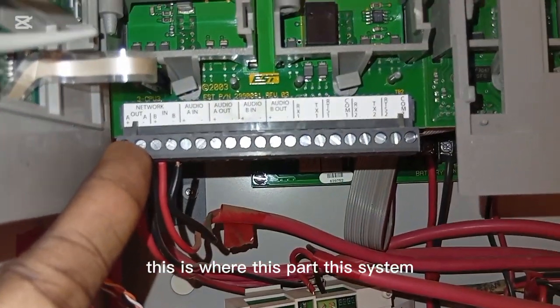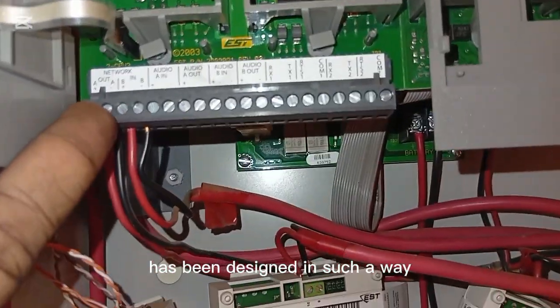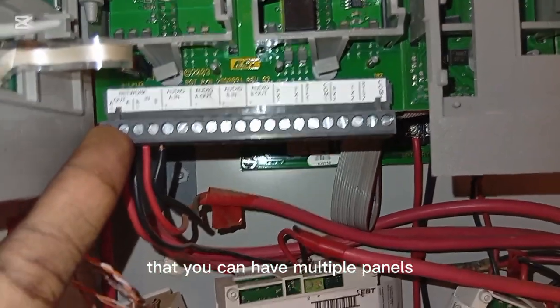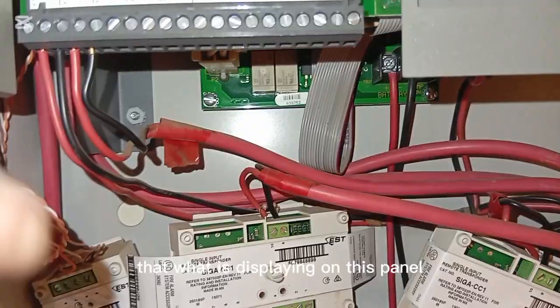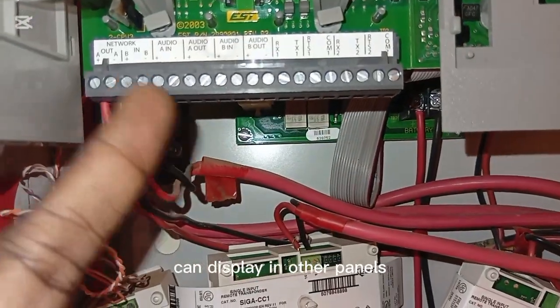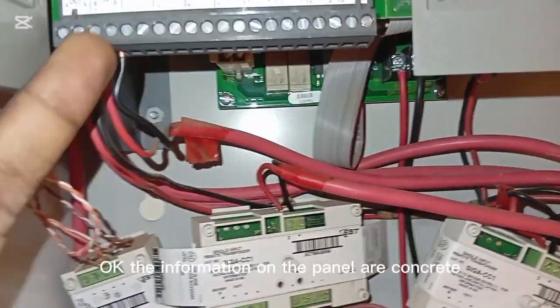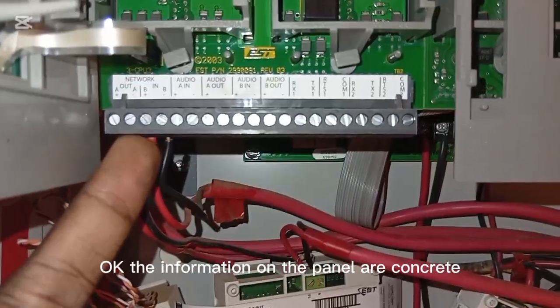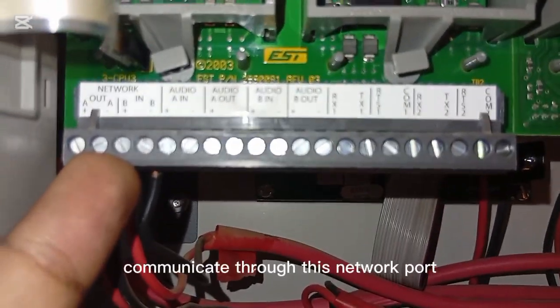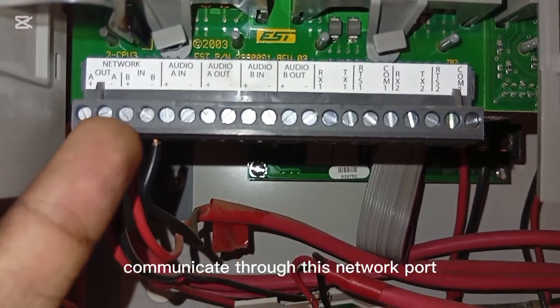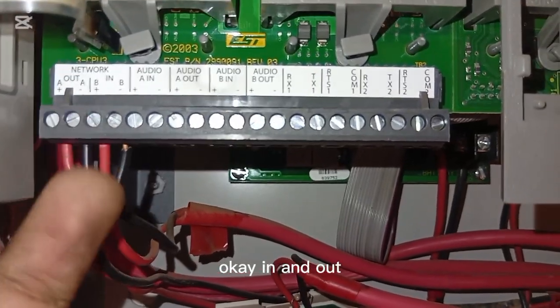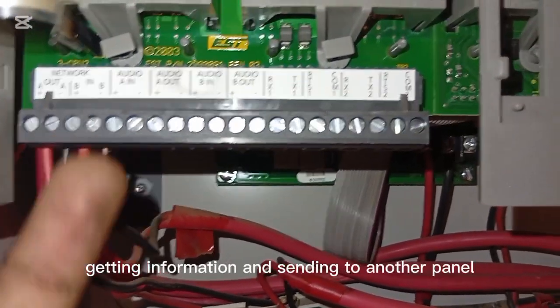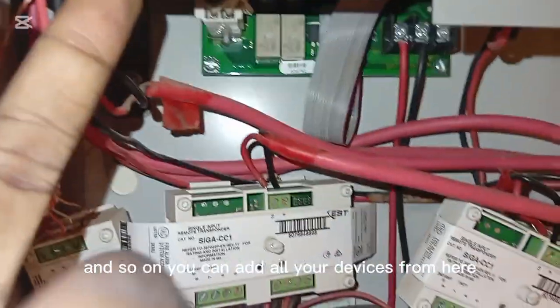This EST3 system has been designed in such a way that you can have multiple panels and make them communicate, so that what is displayed on this panel can be displayed on other panels. The information on the panels is concurrent and the same. You can make them communicate through this network port, in and out, getting information and sending it to another panel, and so on.